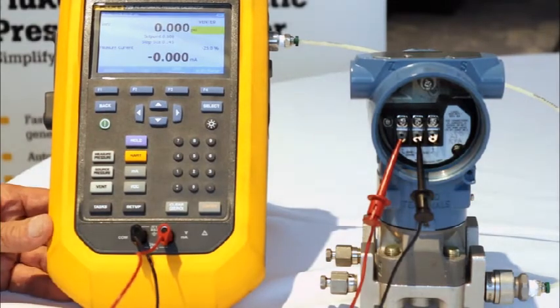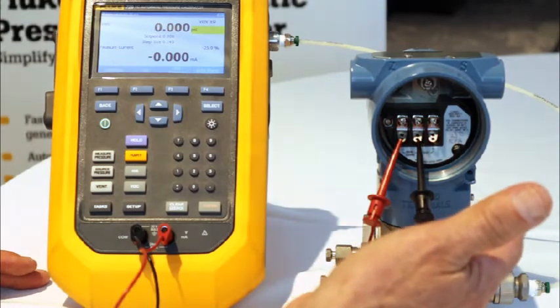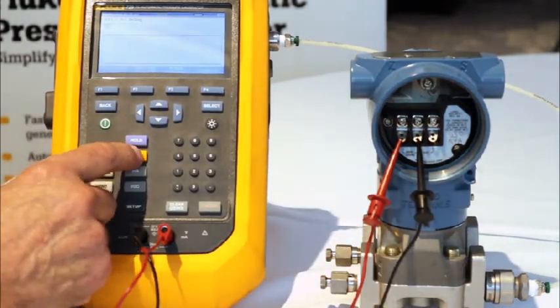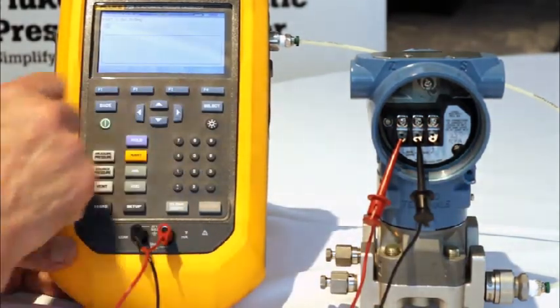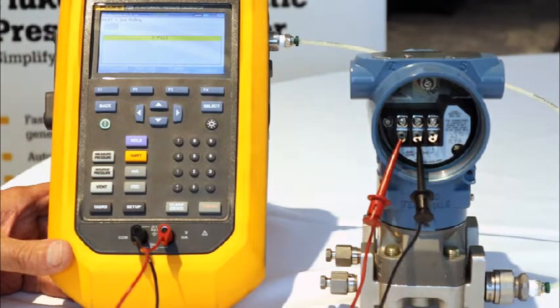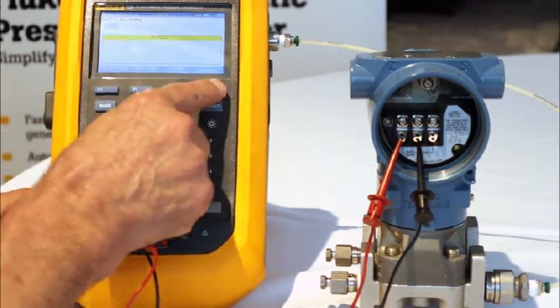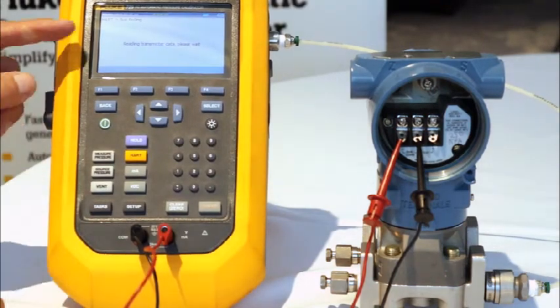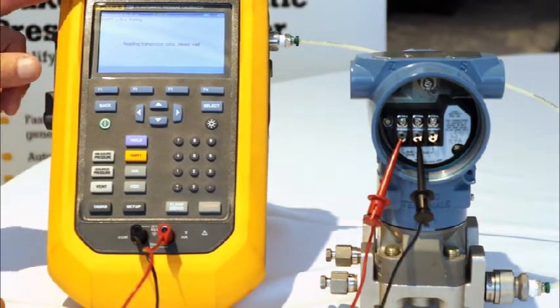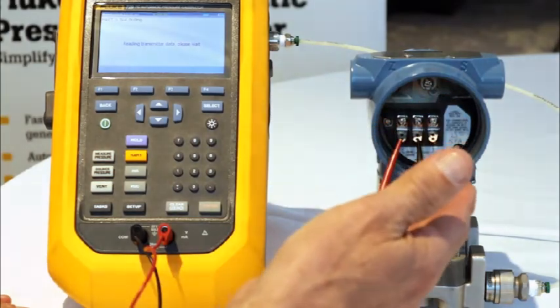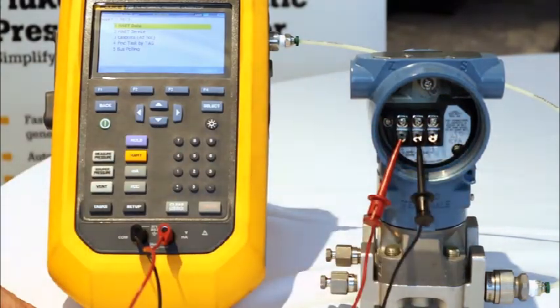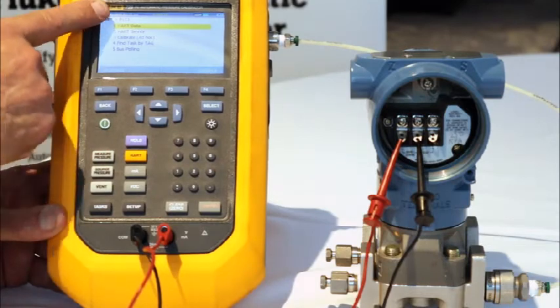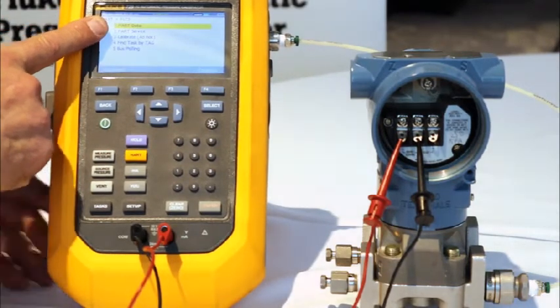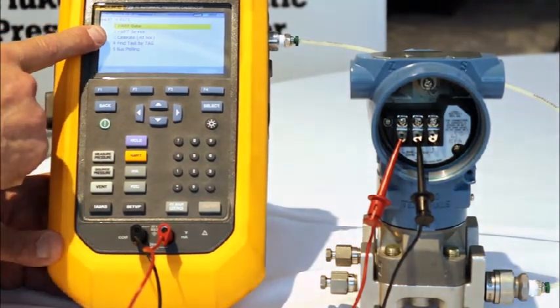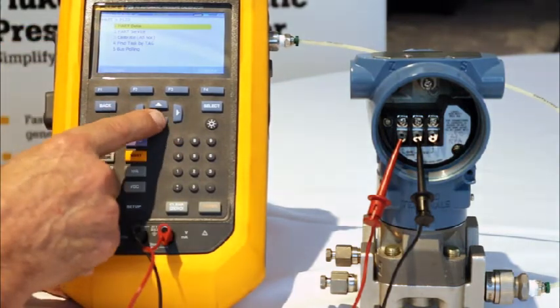Next step, I can use the HART communication built into the 729 to identify the configuration of the device we're going to test. So let's start up HART, turn on loop power, and switch in the 250 ohm smart resistor to tune the loop. Here's the tag number, continue, reading transmitter data. The 729 is collecting the HART configuration from the 3051 to give us the information we need to do the calibration. So I have some options here. I can either look at the data, go in and do service, trimming, etc., or I can do an ad hoc calibration, which I'll do now.